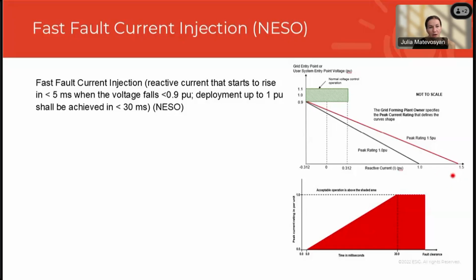response would be. Again, National Grid doesn't require oversizing for provision of grid forming capability, but they require to announce what kind of capability you have. So if there is a short-term overcurrent capability, the generator owner will have to specify it in the documents.